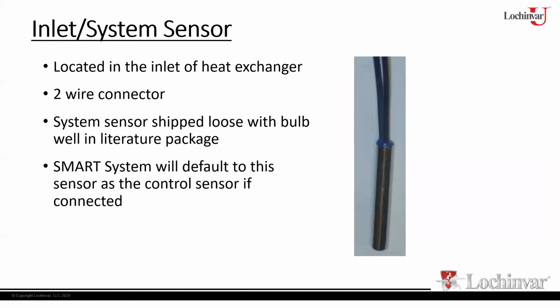So we have an outlet sensor. We've also got our inlet sensor. So the inlet sensor is monitoring the inlet temperature, outlet monitoring outlet. You've got to have them both because the control module also looks at temperature rise. It sees that the delta T becomes too excessive, all right, then it's going to shut the heater off because it says, hey, we've got a flow problem here. We can't have this. So if the delta T becomes too excessive, it's going to shut the unit down. So you've got to have both sensors.